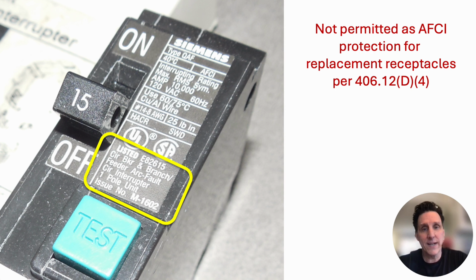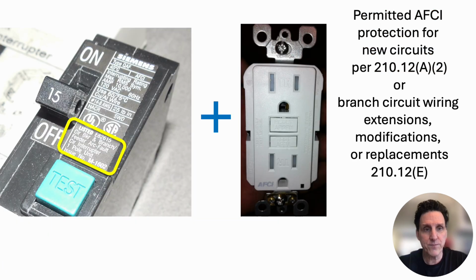Now, as a side note, because you might be wondering, where can I use this type of AFCI breaker? Well, you can use that type of breaker, a branch circuit/feeder AFCI, if you also install an outlet type AFCI at the first outlet.